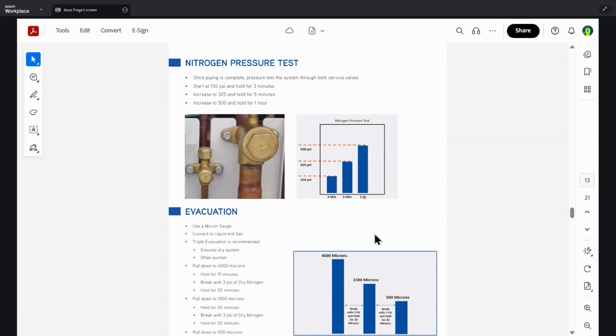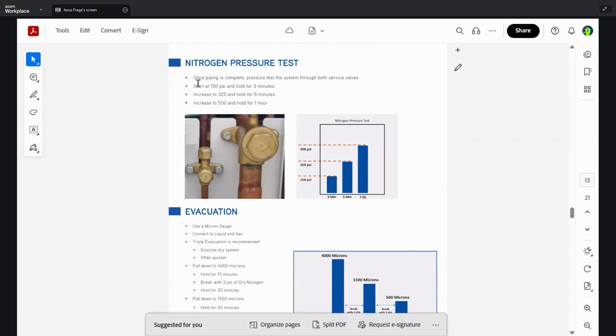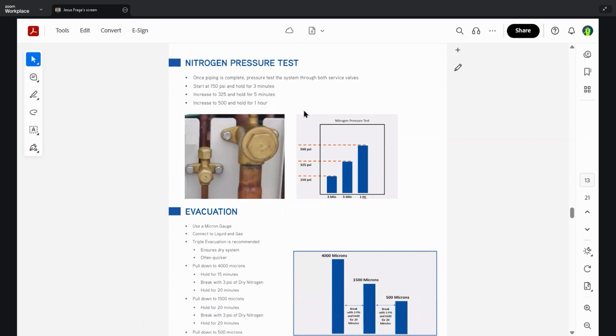So moving on, the nitrogen pressure test. This is another one of those things that pretty much stays the same. So once the piping is complete, pressurize the system through both service valves. Start at 150 and hold for 3 minutes. Increase to 325 and hold for 5 minutes. Increase to 500 and hold for 1 hour. And here's a chart on how to do that. Duration, examples.